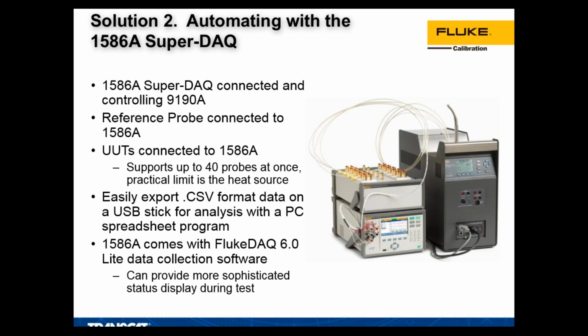It's a readout used for measuring thermocouples and RTDs, great for calibrating in large volume if you need to. That DAQ-STAQ is the instrument on top of the 1586A in this picture, and I can connect up to 20 different probes to the top of it and calibrate them. That's kind of cool.